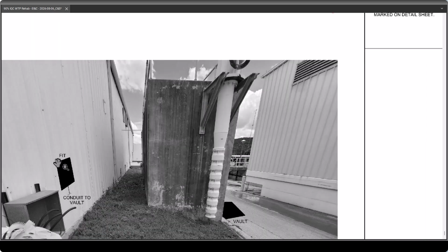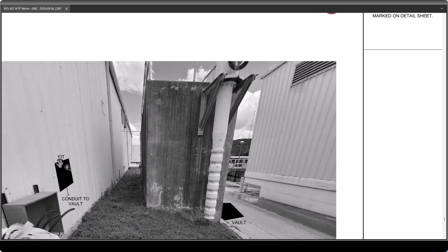All right. She did call out a shield, FIT with mount and shield, which the first three times I read that, I read it as fit with mount and shield. Good point. It didn't dawn on me you were trying to say this is the flow indicator transmitter, because technically the flow transmitter's down here and this is the indicator.